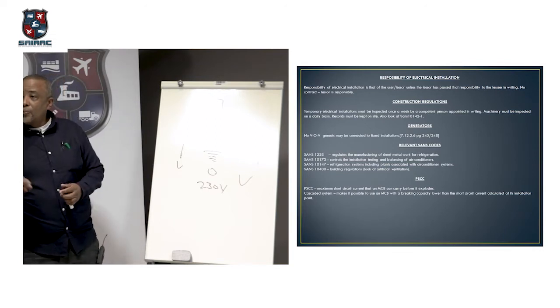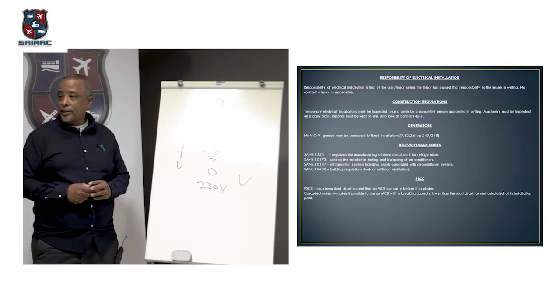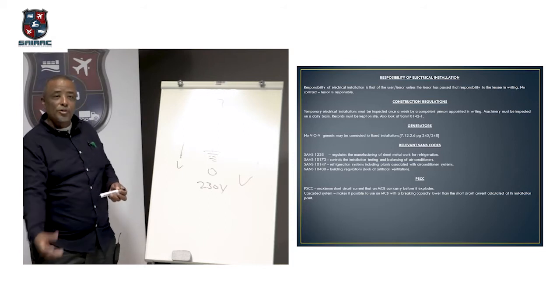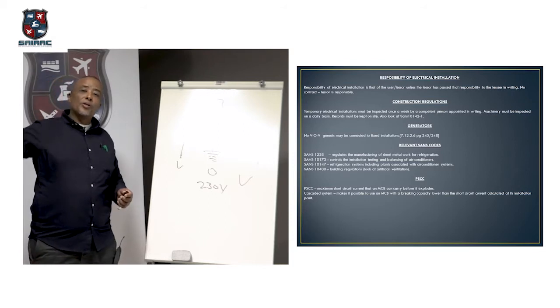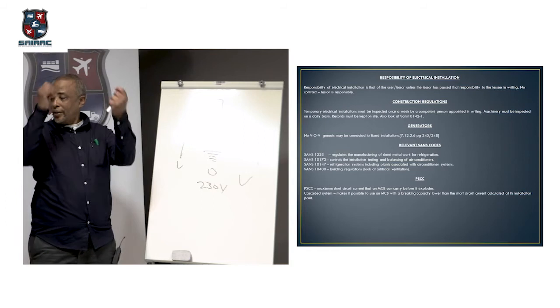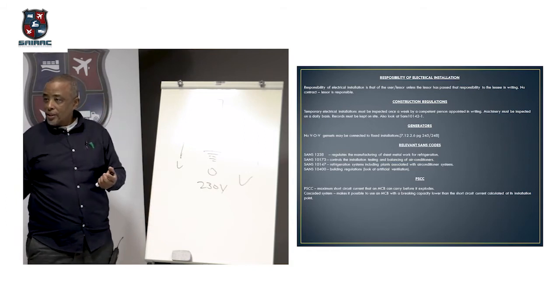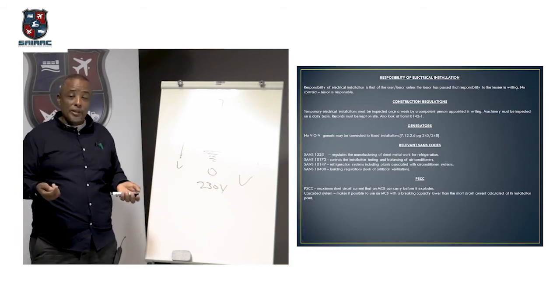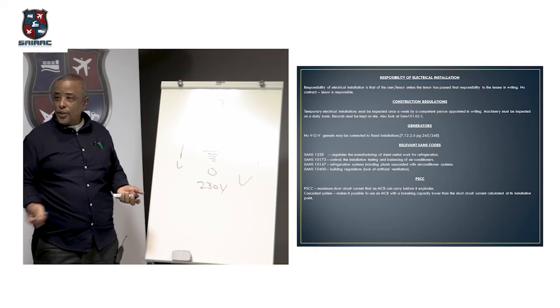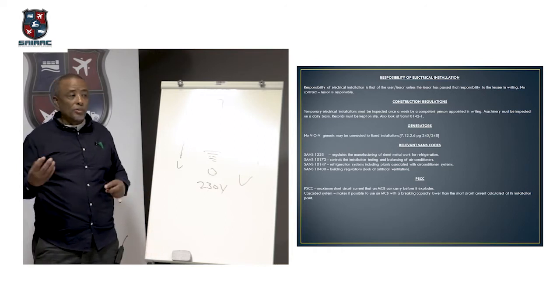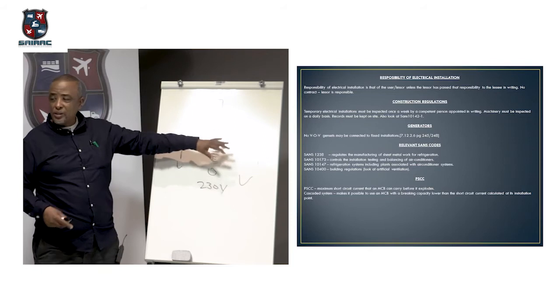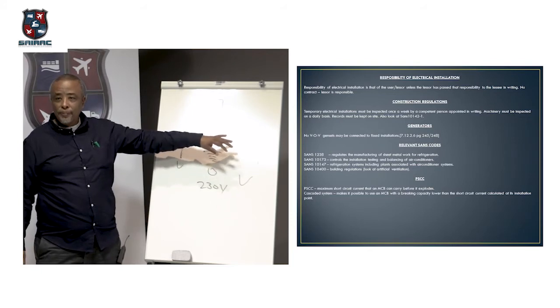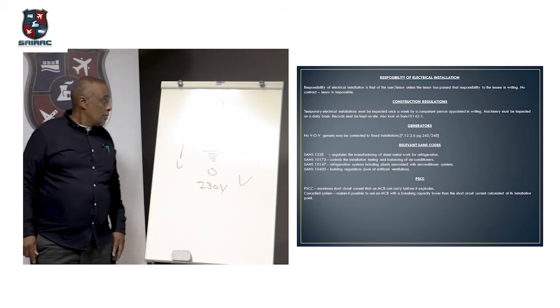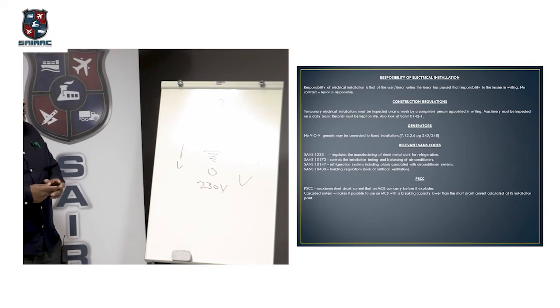I've heard how one guy actually died because the guy plugged the generator into the wall and it went through the transformer and onto the line while the guy was working on the line, knowing that it's dead. It became energized and the guy died because of a generator. Okay, so if you have been using those generators, just please don't use them for home. Okay. All right. Any questions?